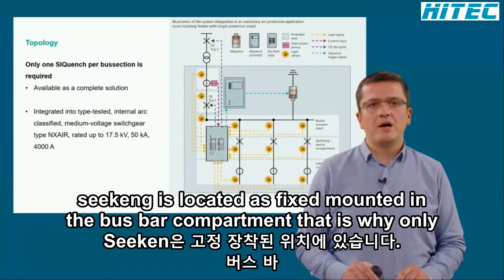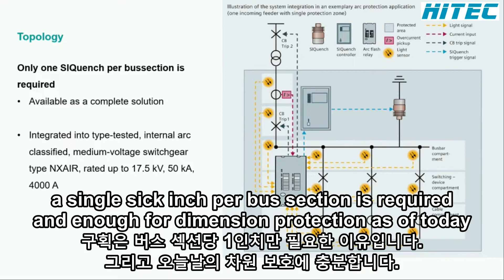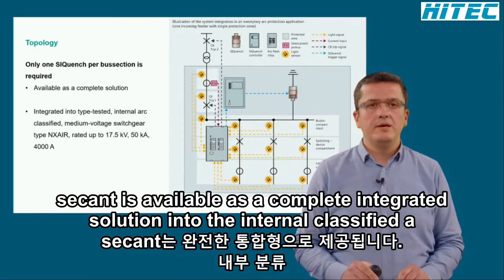SIQuench is located as fixed mounted in the busbar compartment. That is why only a single SIQuench per bus section is required and enough for the mentioned protection. As of today, SIQuench is available as a complete integrated solution into the internal arc classified air-insulated medium voltage switchgear type NX Air up to and including 17.5 kV and 50 kA.